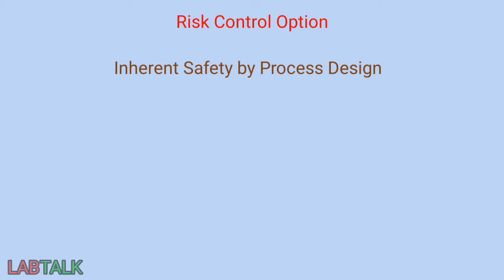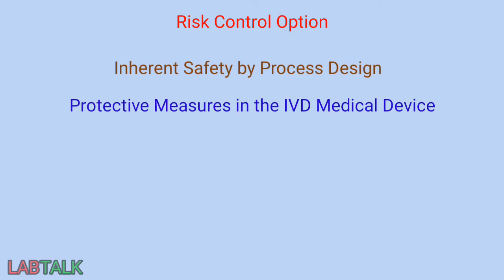The next option for selecting risk control measures is protective measures in IVD medical devices. If the risk is related to the IVD medical device, we have to find out whether there are any risk control measures in the IVD medical device or equipment itself. Many times, alarms, failure detection methods, and fail-safe mechanisms are in place in most medical devices or laboratory equipment, and this can be used as a risk control measure.